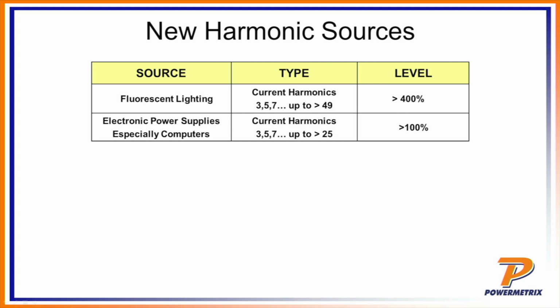If we talk about new harmonic sources, these are things that we see a lot more nowadays. What we find is lighting in particular can cause a lot of harmonic energy, and we're going to give you some very specific examples. Fluorescent lighting, for example, can generate up beyond 400% of harmonic energy. And so as such, that's a big problem.